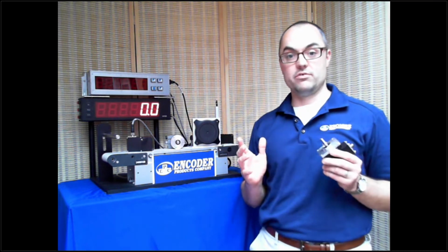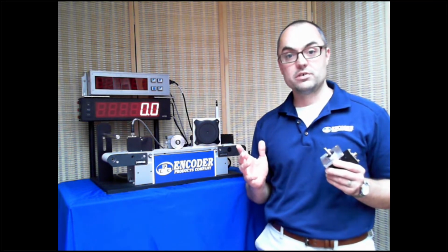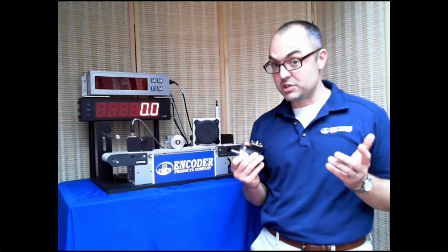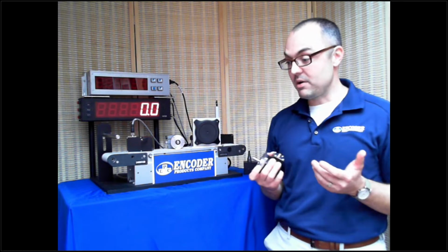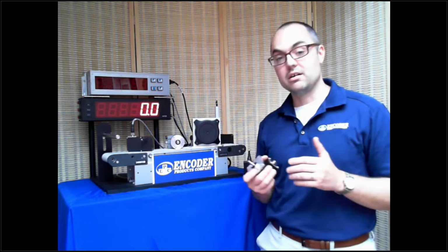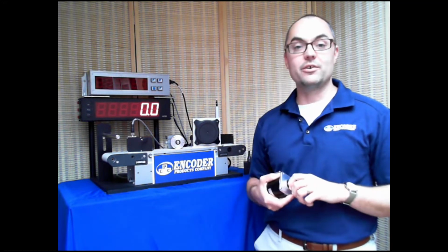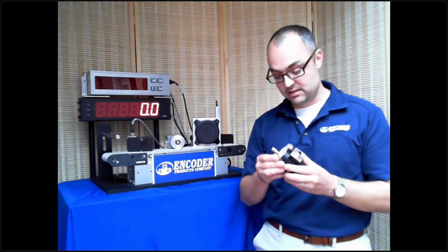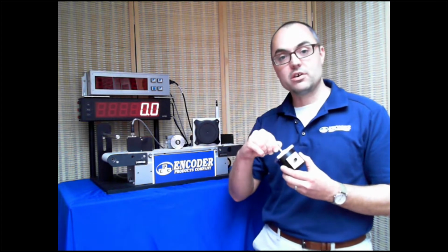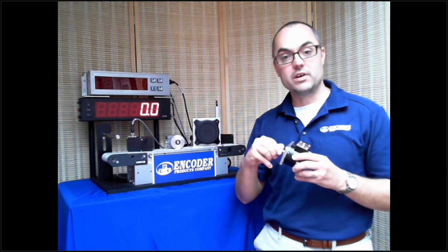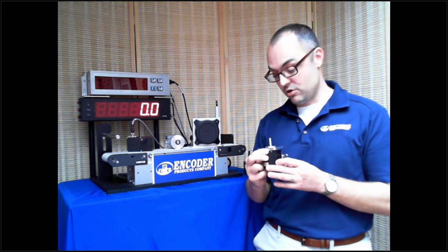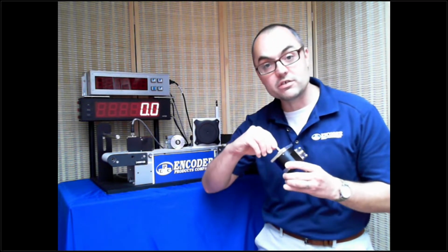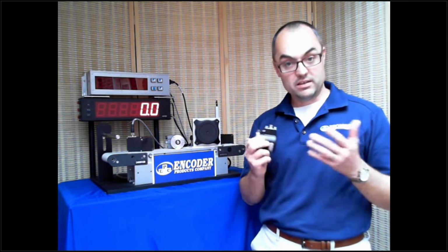There's two flavors of encoders, incremental encoders and absolute encoders. Incremental encoders operate on a very simple principle. They create pulses. Think about when you were a kid. You put a playing card in the spoke of your bike, and you rode your bike around and annoyed your parents. Well, that's what an encoder does, except it does it with light and lines on a disc. When I rotate the shaft of an encoder, the light is interrupted and it creates pulses. When you buy an encoder with 1,000 lines on the disc, one exact rotation of this shaft will create 1,000 pulses.